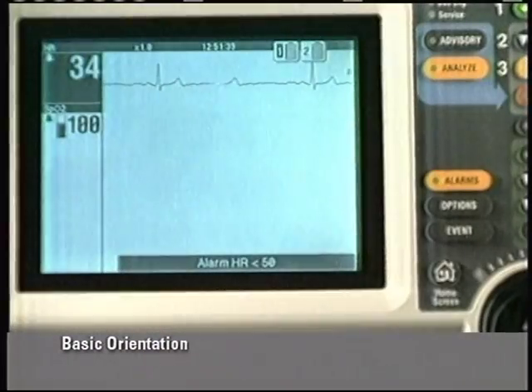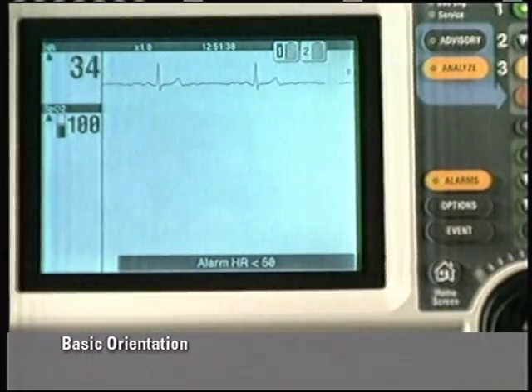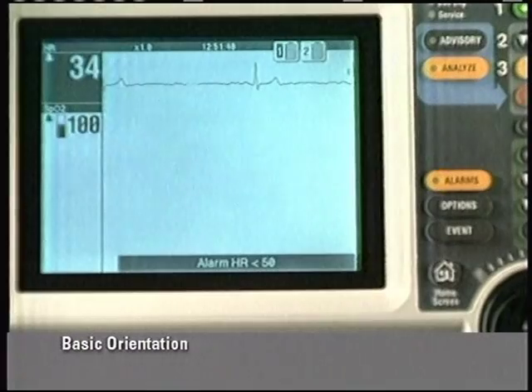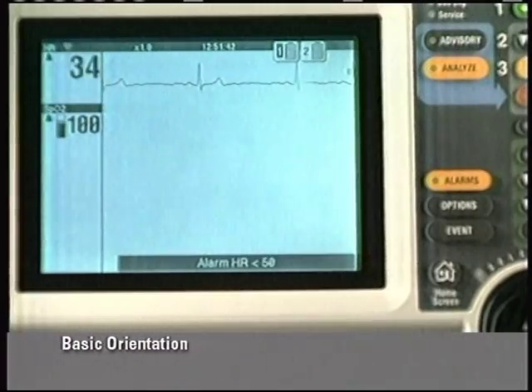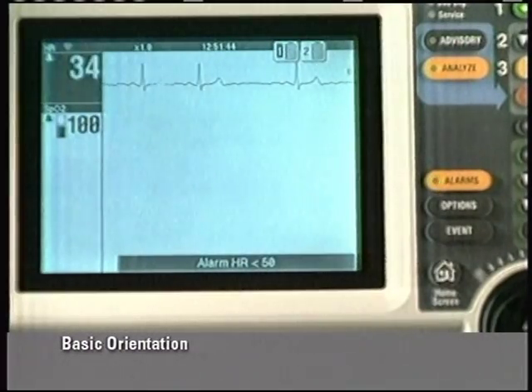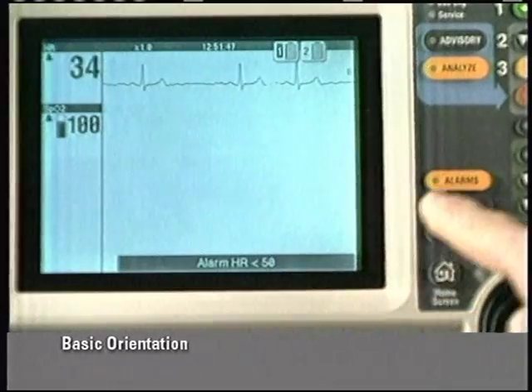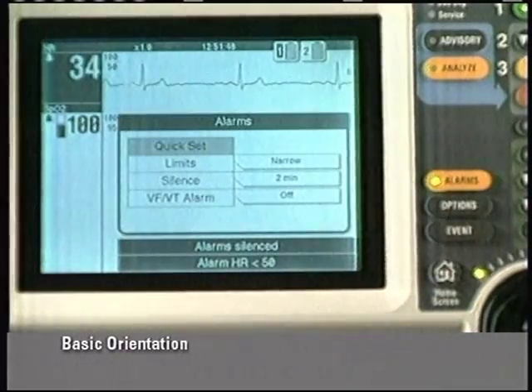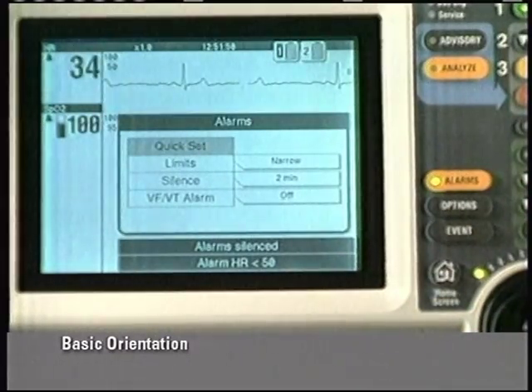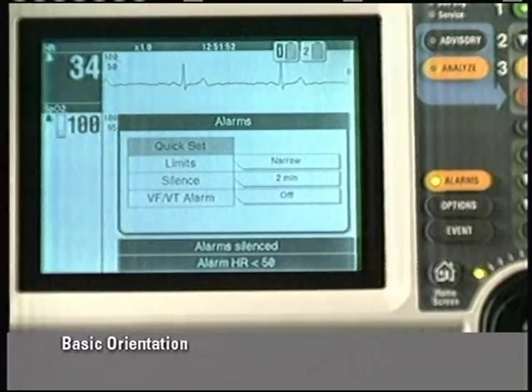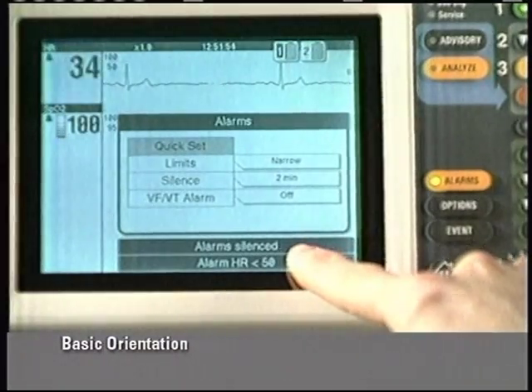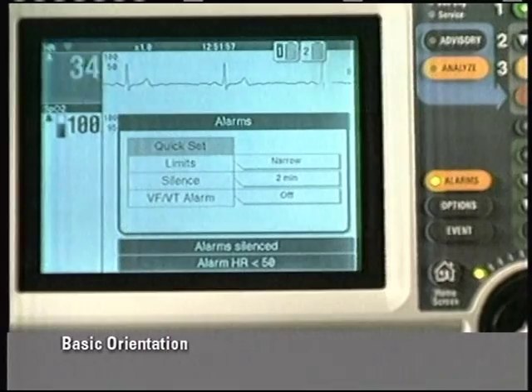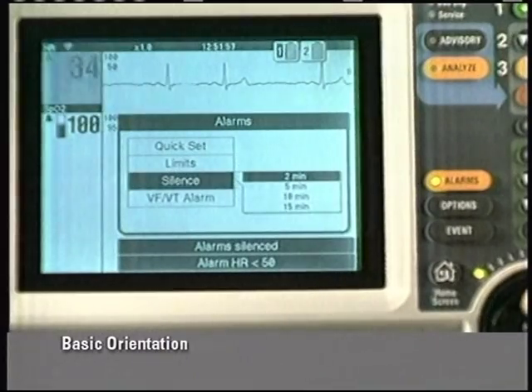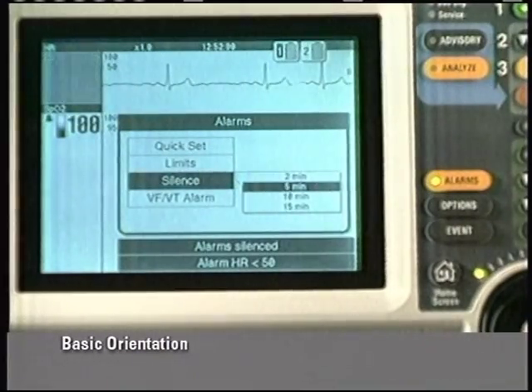When an alarm limit is exceeded, a continuous tone sounds, the affected parameter and Alarms button flash, and a message appears. To manage the alarm, first press Alarms. This silences the alarm for 2 minutes. The message Alarms Silenced appears. To silence the alarm for longer than 2 minutes, select Silence on the menu and the desired length of time.